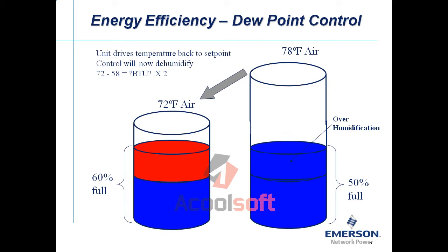So you can easily see where this can get into a repetitive cycle, especially in a low load condition, where the temperature is fluctuating, the compressors are activating, it's too much, they turn off, the temperature climbs, and you get into a cyclical temperature change, which kind of drives the humidity crazy and increases your energy bill.